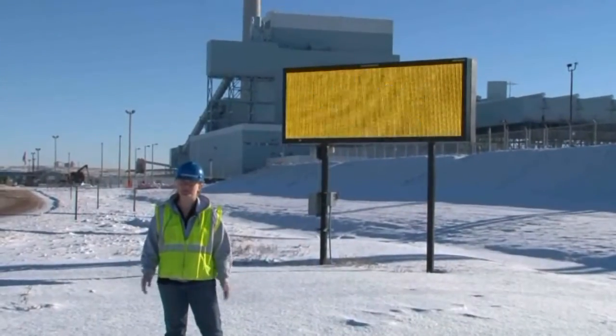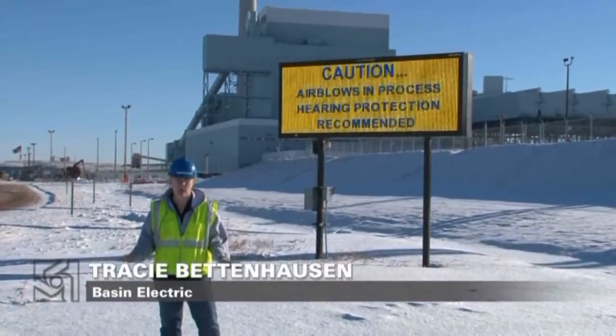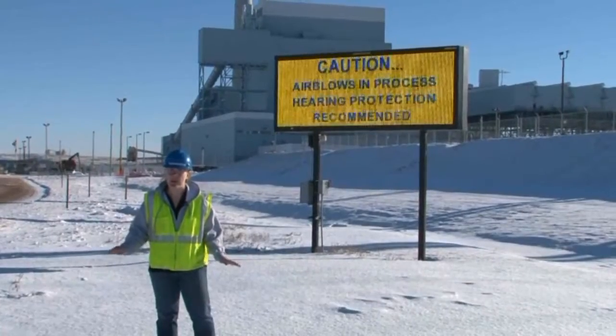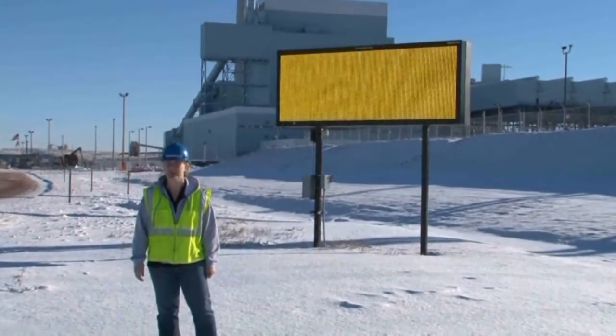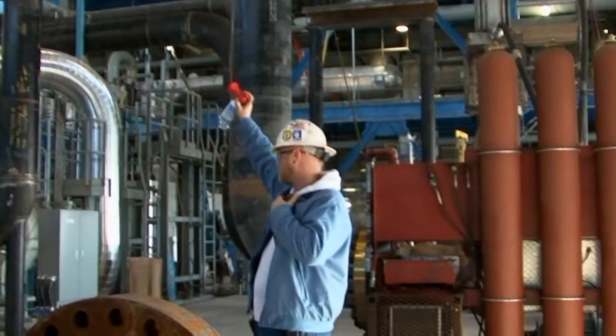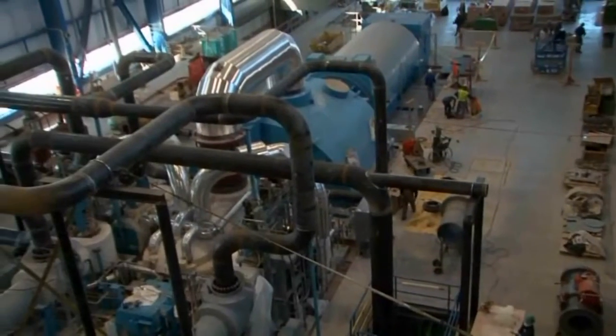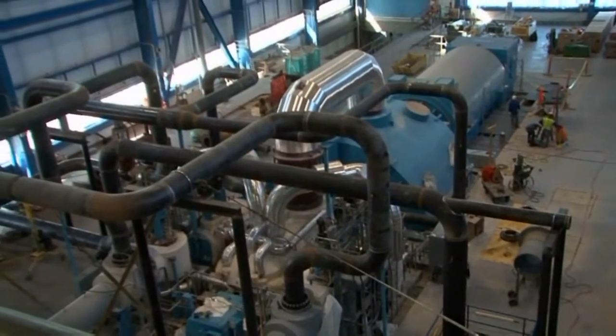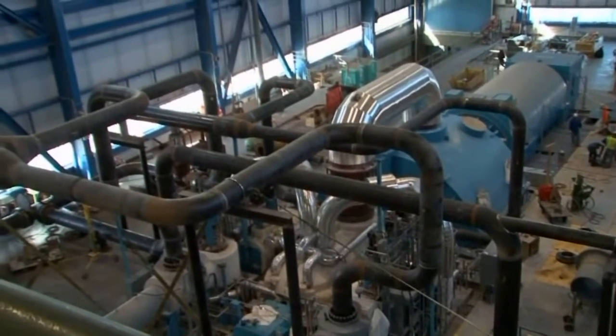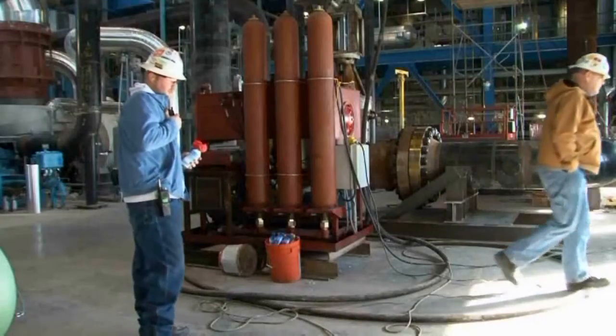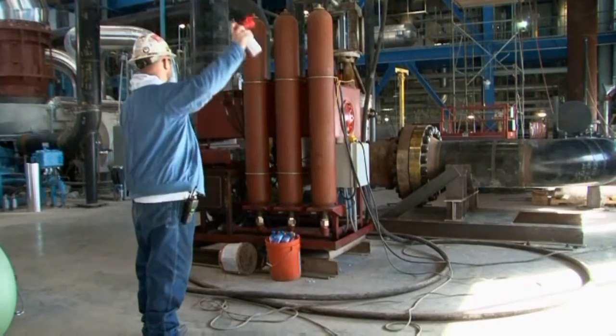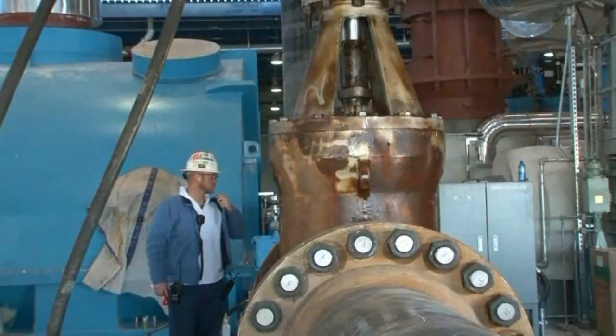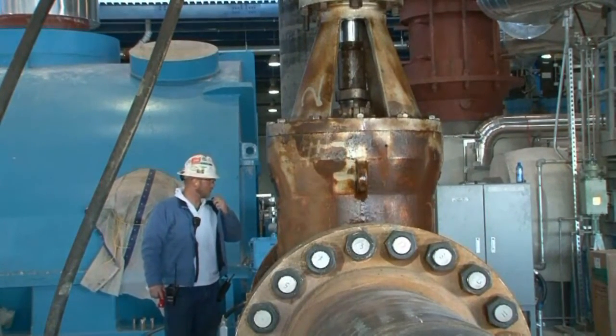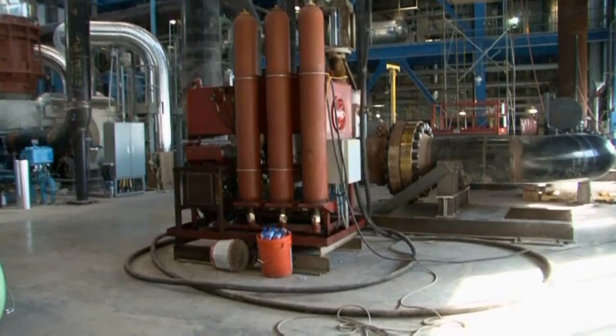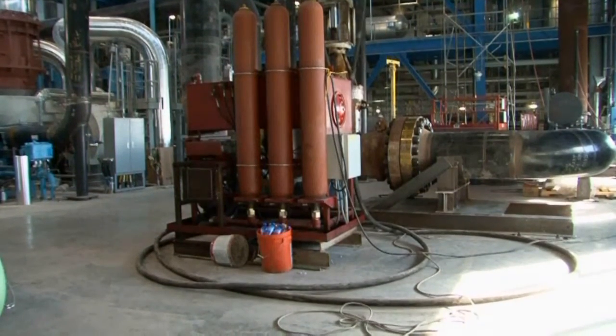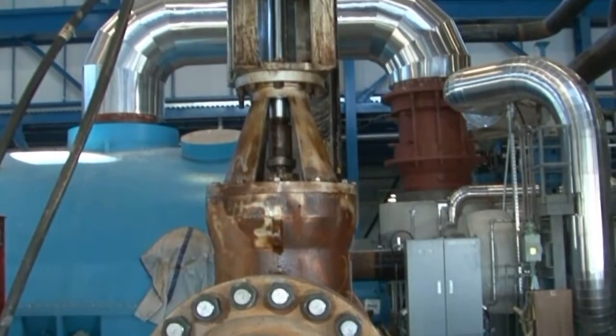Ever since New Year's, the turbine deck here at the Dry Fork Station has been rumbling. It happens about once an hour, and each time workers get 3 minutes warning. 3 minutes till air blow. That's the sound that's come 97 times up to this point. The signal, another air blow at Dry Fork Station, is 3 minutes away. 1 minute to air blow, 1 minute. It lasts only about 20 seconds, but this is the step needed to clean out the pipes before Dry Fork Station can start generating electricity.